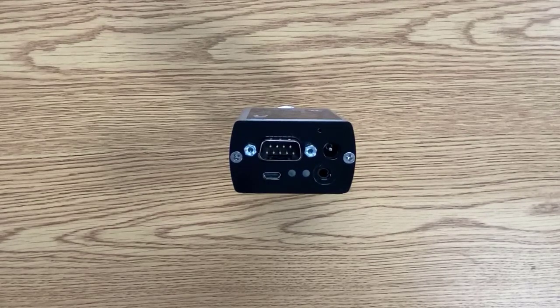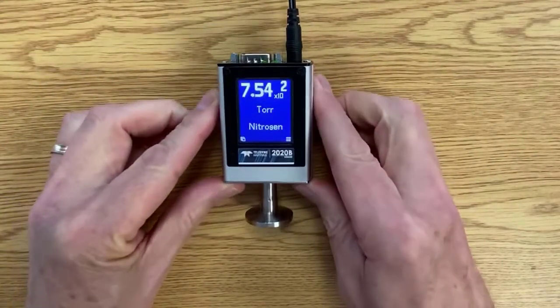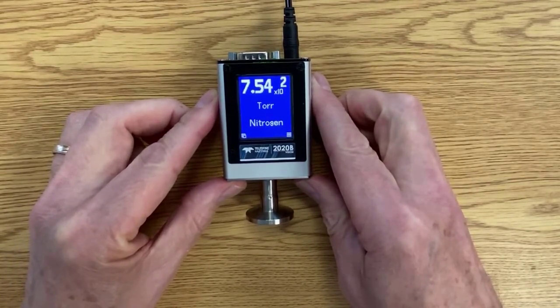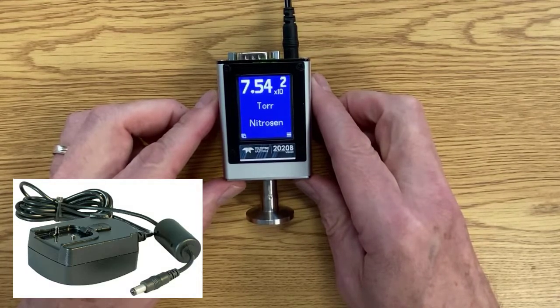Now, let's get the HVG-2020B powered up. The easiest way to get started is to simply use the 24-volt barrel jack. Plug in here. And when we plug in, we instantly get an accurate reading at atmospheric pressure. You can get the power supply from us or buy your own.